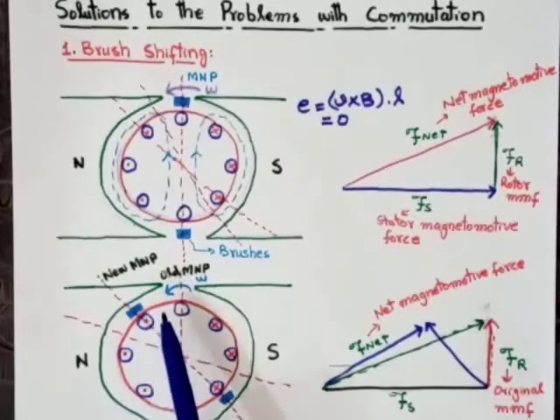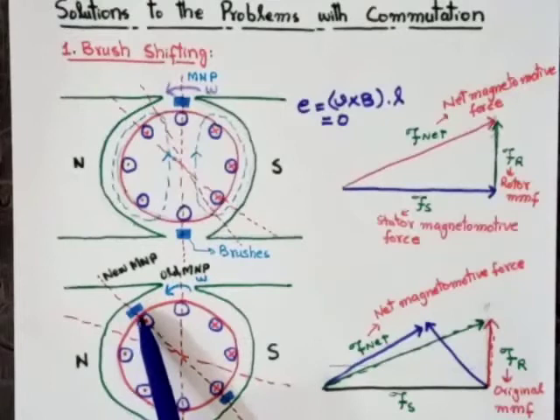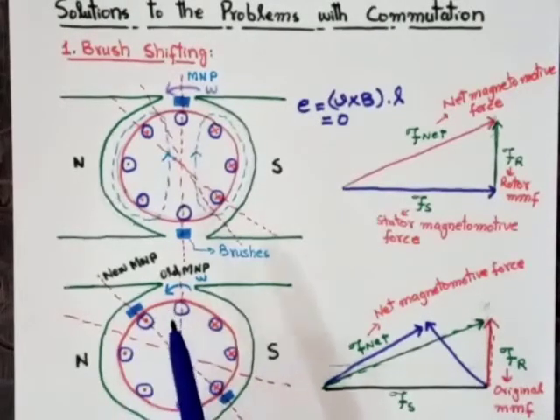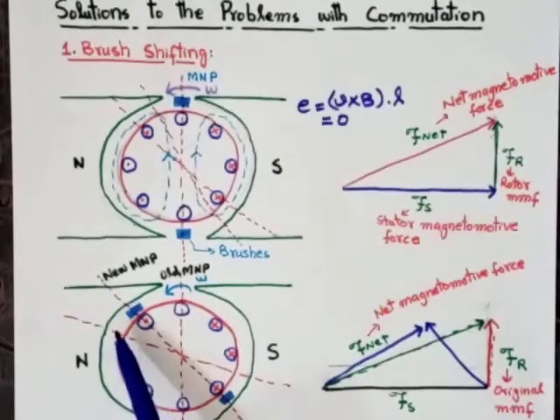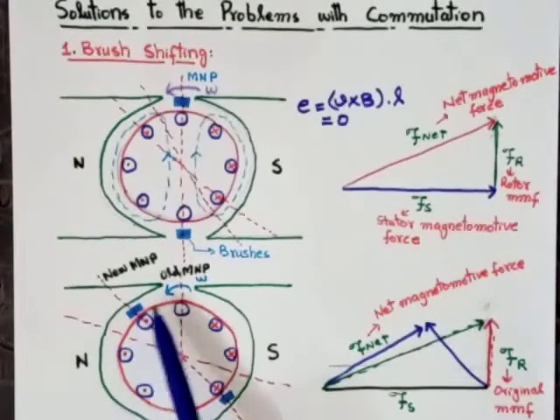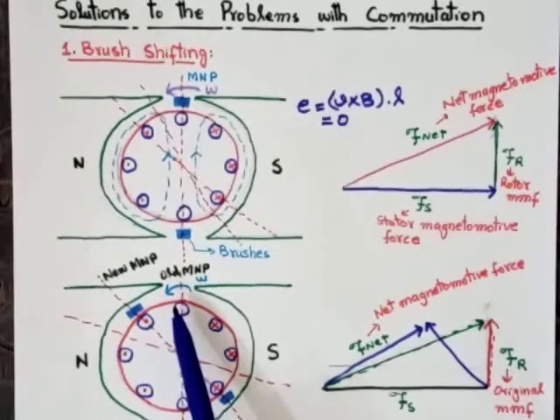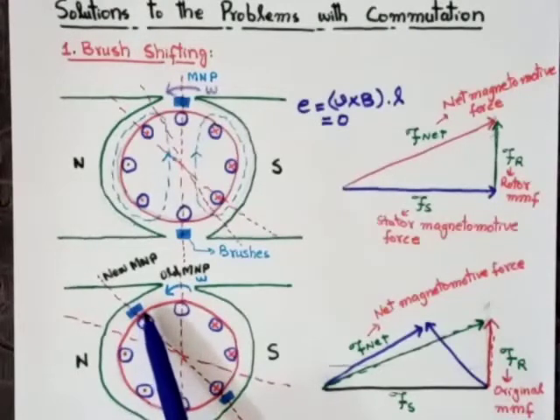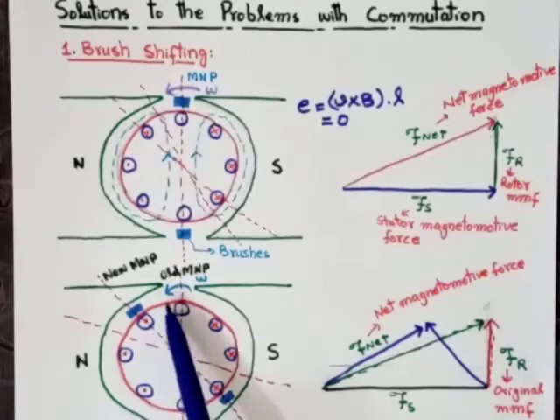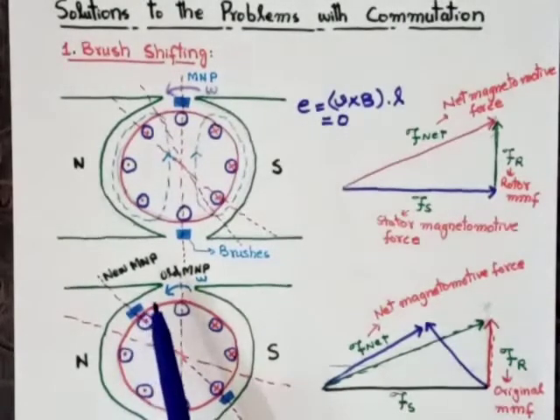It looks like a good option, but it also creates some problems. The neutral plane changes its position with load variation — if we increase the load, the magnetic neutral plane shifts further; if we decrease the load, it shifts in the opposite direction. It means the magnetic neutral plane is dependent on load. Then we would have to hire someone to constantly adjust the position of the brushes, because when we change the load, the current across the rotor conductors changes and so does the position of the magnetic neutral plane.